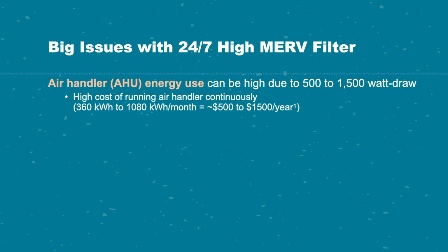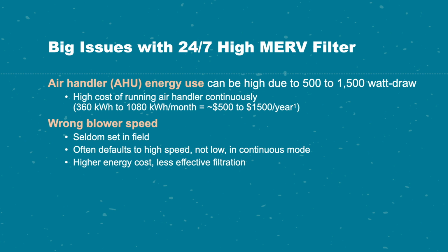The cost is invisible. You can't easily meter the cost of running your air handler, and it can be really high. So if you run it continuously, we're talking potentially big bucks. There are a few that we've seen that are less than 500 watts, but we just recently ran into one that was 1200. So you're talking a lot of very high costs to run a typical air handler 24/7. They're usually set on high, and they're very seldom set in the field. They're set on factory default.